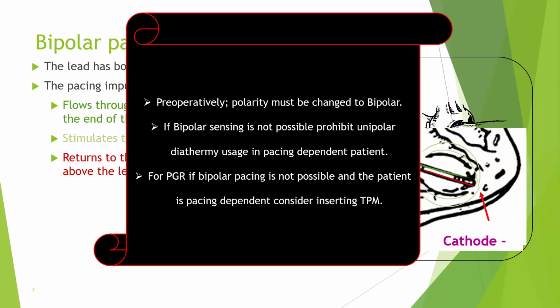If bipolar sensing is not possible, then prohibit unipolar diathermy usage in a pacing dependent patient, and make sure that this patient has constant pacing throughout the procedure, maybe by putting a magnet and canceling any sensing. For a generator change, if bipolar pacing is not possible, then you must put a temporary pacing wire, or you have to be very quick, because the moment you take the pulse generator from the pocket, the patient is going to go to asystole because he lost the positive electrode for the pacing.